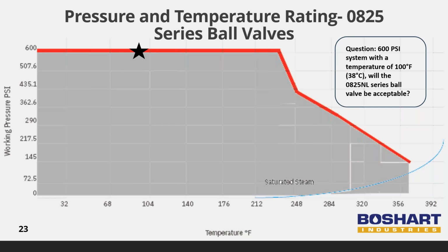You will notice that the pressure rating does not drop until somewhere between the 212-degree Fahrenheit and 248 degrees Fahrenheit, at which the pressure rating drops at a significant rate as the temperature increases.